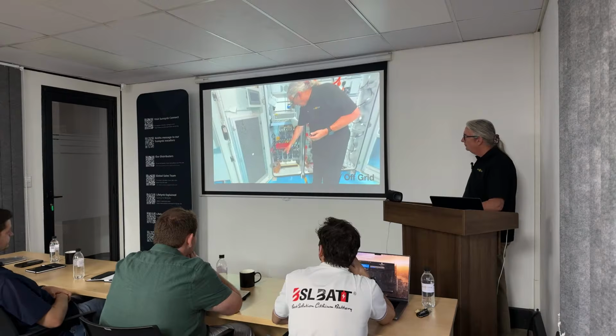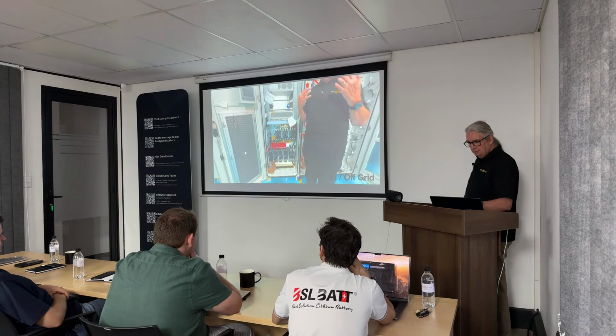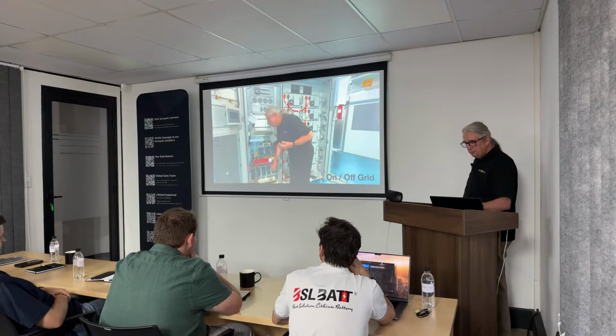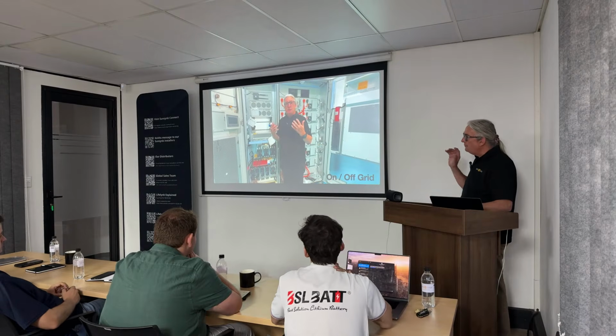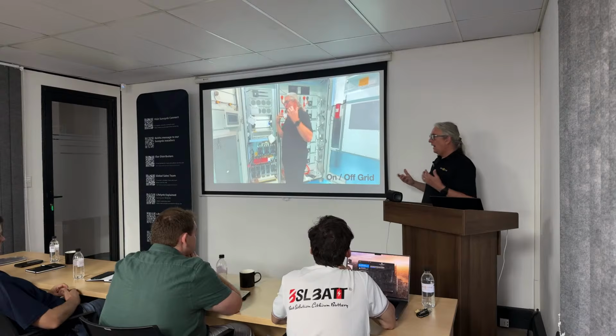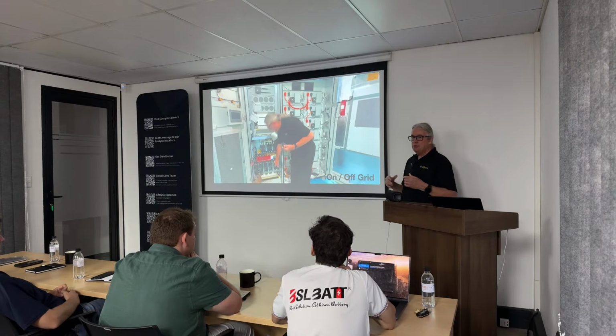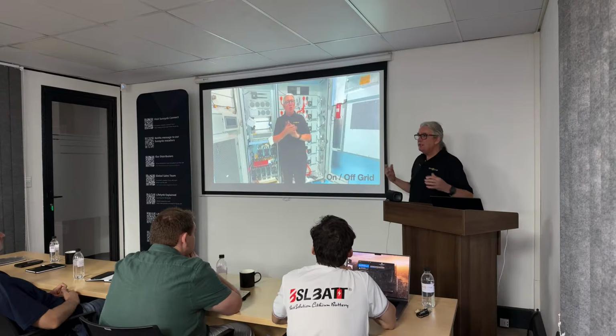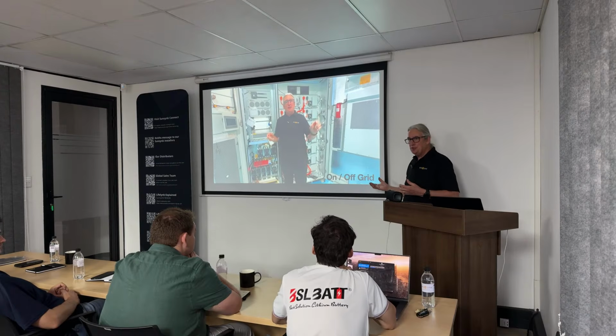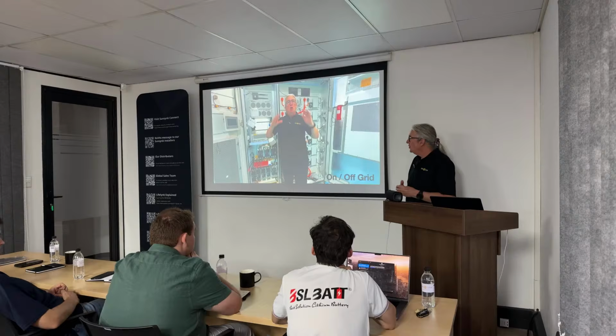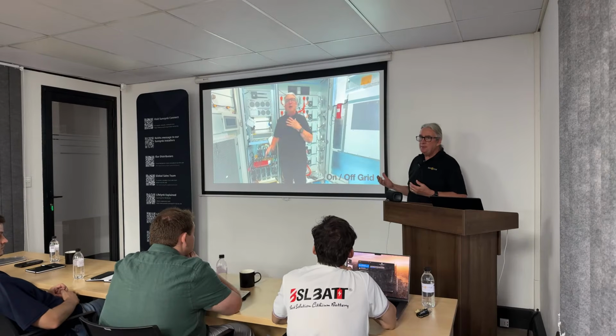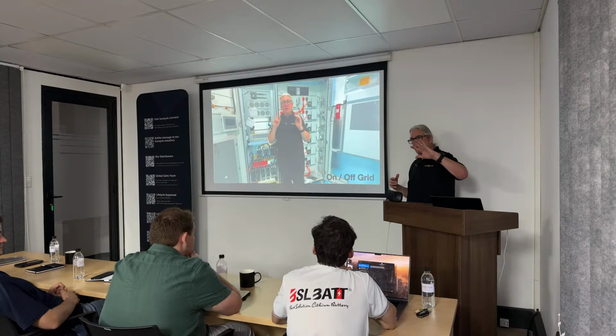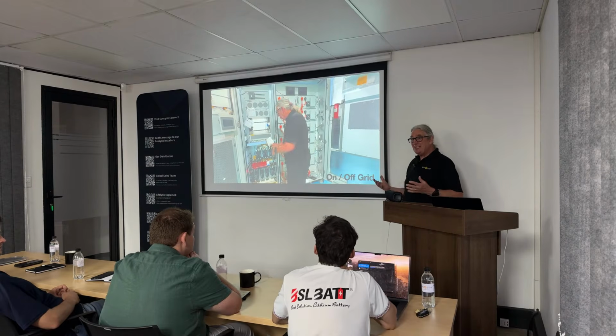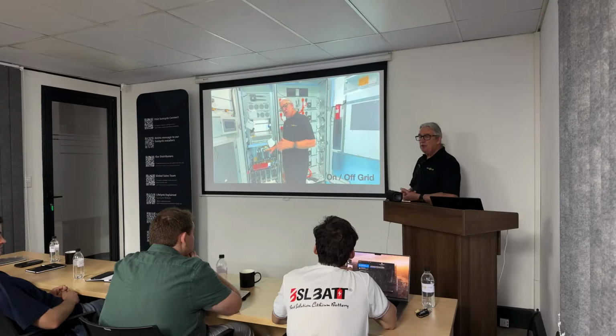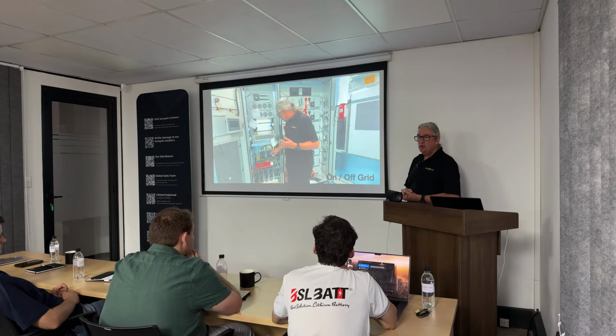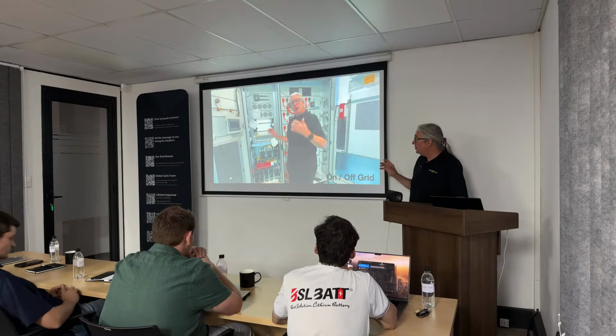On the bottom here, on the power hub, you've got 4 channels. They are your MPPT inputs. They've all got separate DC isolators. The MPPT inputs are quite high power, and you would have to use a combiner box with diodes. I wouldn't suggest you go and connect the solar panels directly to them. Each unit is, say, a 60 kilowatt MPPT. Then you would need 5 per channel. So it's basically a 10 channel combiner box split into 2 with diodes, with surge protection and everything. So you definitely need to use that.